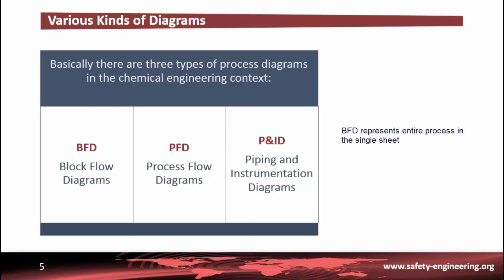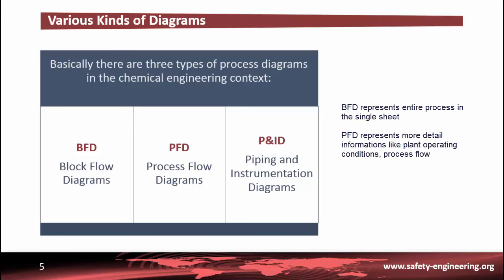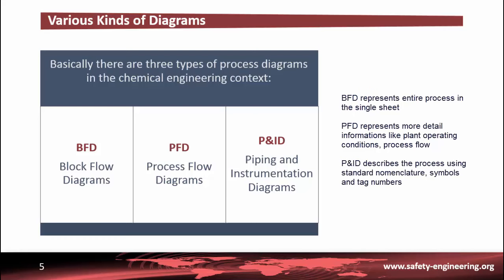In short, a BFD represents the entire process in a single sheet, whereas in the PFD you can find detailed information like plant operating conditions or process flow. It uses symbols to represent the equipment. P&IDs provide more detailed information compared to the previous two drawings. They use standard nomenclature, symbols and tag numbers to fully describe the process.